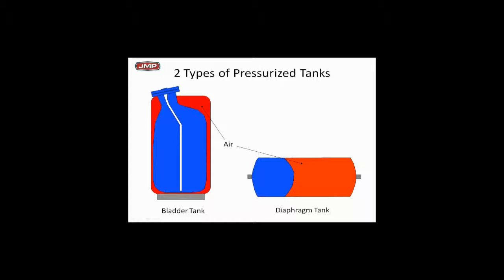There are two types of pressurized tanks. The bladder tank has water in the bladder and it's pressurized — the bladder can be taken out and replaced. The diaphragm tank is a throwaway; you cannot replace the diaphragm. That's the difference between the bladder and the diaphragm — it's about that simple. We ship them from the factory at 12 pounds. Remember, you're going to have to pre-charge these tanks on the job site to the makeup pressure at that elevation to make sure when you start off, they're 100% full of air.